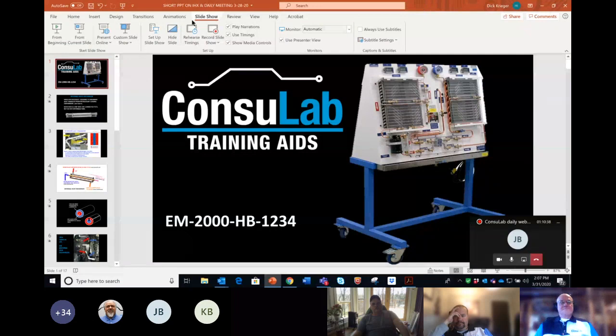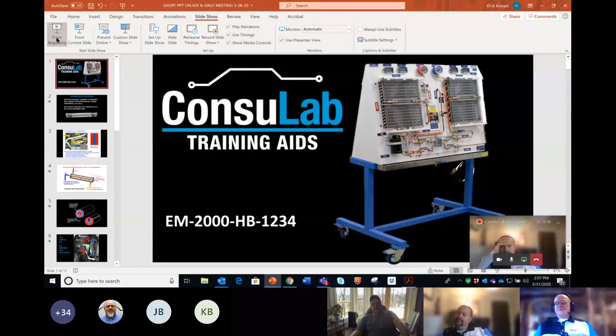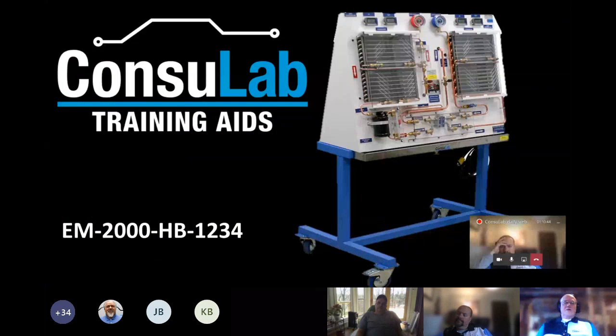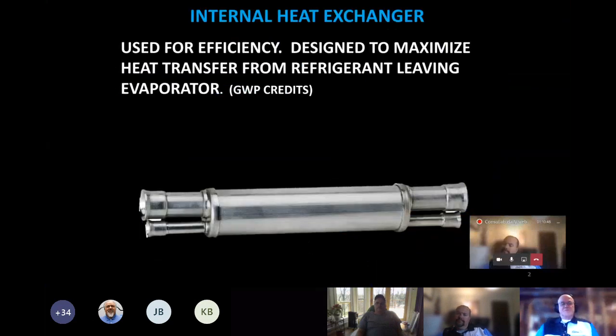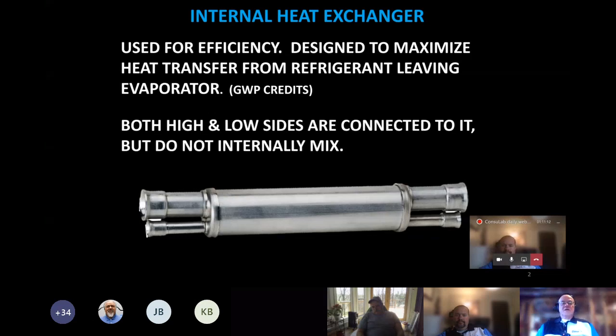Okay. This is the internal heat exchanger. This is not one from a car, but it's a representative picture with the 2 large and 2 small lines. Commercial and industrial refrigeration has been using these for years. This is not a new technology, but because of the energy credits, now OEMs are starting to use it because they get EPA credits for system efficiencies. Both high side and low side are connected to it, but they do not internally mix.